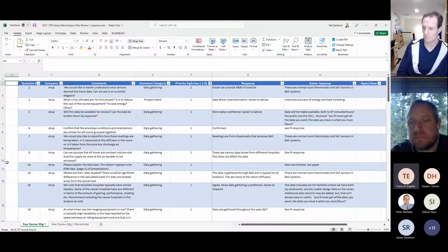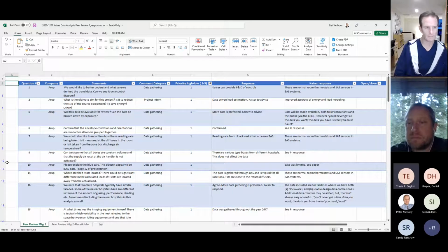That's where we need to go with this data: design for the profile and not just the peak. I expect the room zone sizing will largely stay the same, but the shaft sizing is going to change, the air handler sizing is going to change, and the turn down of that air handler is going to change.